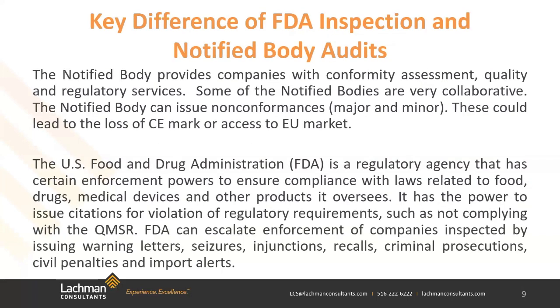So the next slide, we're just going to go over some of the key differences between an FDA inspection and a notified body audit. The notified body serves an important role for a company. They perform the assessments to ISO 13485 and to the regulation MDR 2017/745. That's how they get a CE mark.